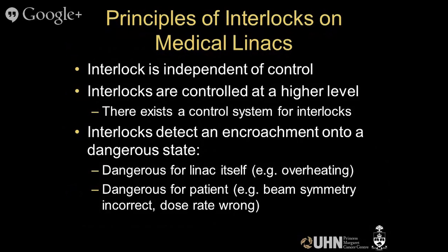There are some principles about interlocks and medical linacs that have been developed since then. Some of the principles are that the interlocks are independent of the control system. The control system's job is to set the state of the machine, and then independently the interlock system says, yes, this is what we wanted, or this is not what we wanted, and the two of them don't interface with each other. And the interlocks are controlled at a higher level than the control system. The interlock is kind of like the goalie. It has to be at a level where it can't be interfered with by any of the other control systems. So there's a hierarchy of controls, which is important in safety systems.